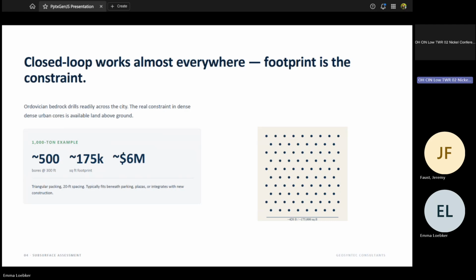I mentioned earlier that closed loop systems can be installed pretty much anywhere — they're highly adaptable — but one of the challenges is they're expensive and require a large footprint. You only get a small amount of capacity per borehole. So if you're trying to heat and cool a system that needs 1,000 tons, you might need 500 boreholes, and if those are spaced 20 feet apart, we're looking at 4 acres. In an urban setting, you don't always have 4 acres of green space to devote to a closed loop system, and that might cost on the order of $6 million.